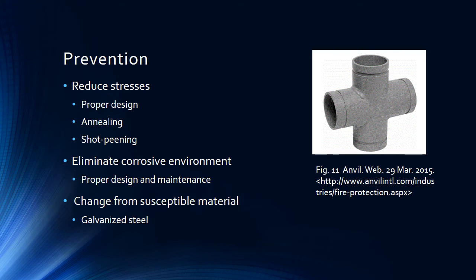Another option would be to eliminate the corrosive environment, which can be done through proper design and proper maintenance. Finally, you can change from the susceptible material altogether and use a galvanized steel pipe instead of a traditional black steel pipe.